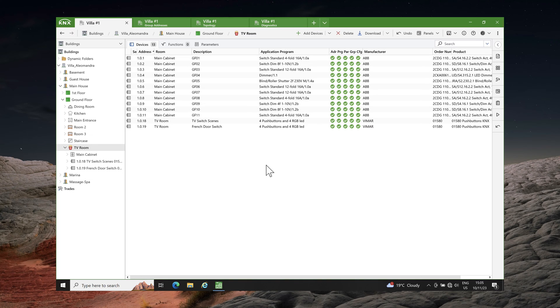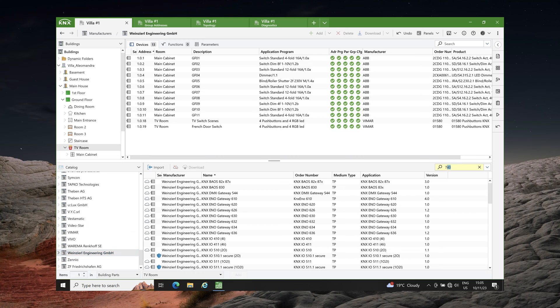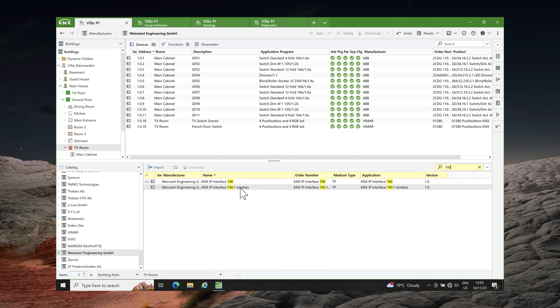The wireless interface is truly plug and play like a KNX USB interface. Of course, if you want to change the device's parameters, it is possible by adding the device in your project. To do so, open the catalog panel, navigate to Weinzierl, search for 740, and add the 740.1 interface to your project.